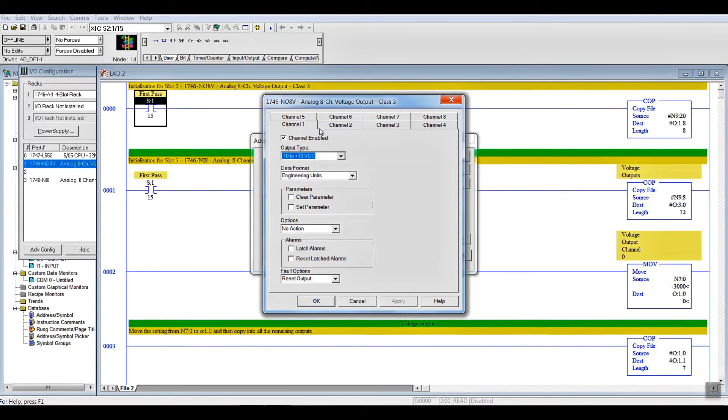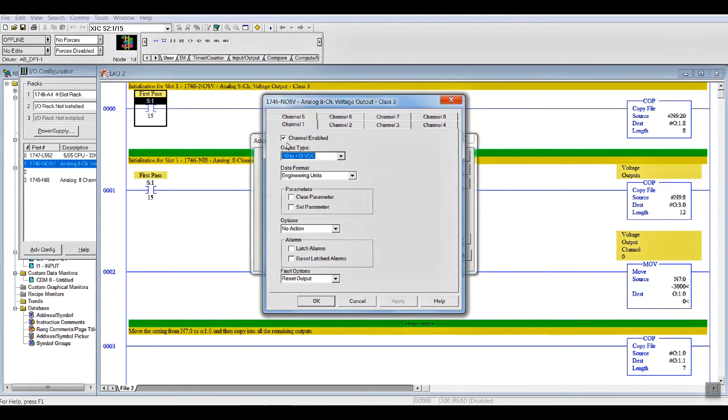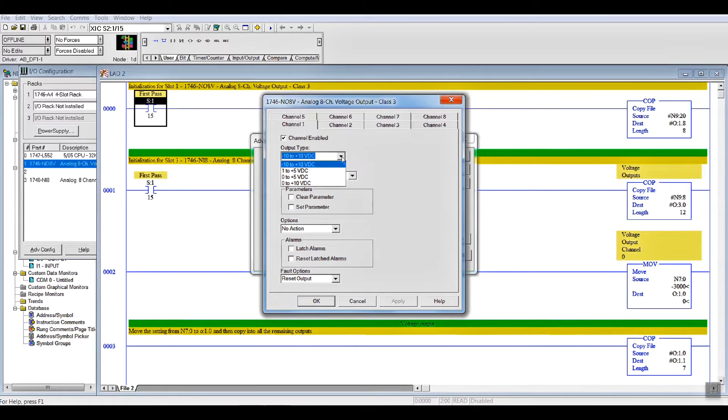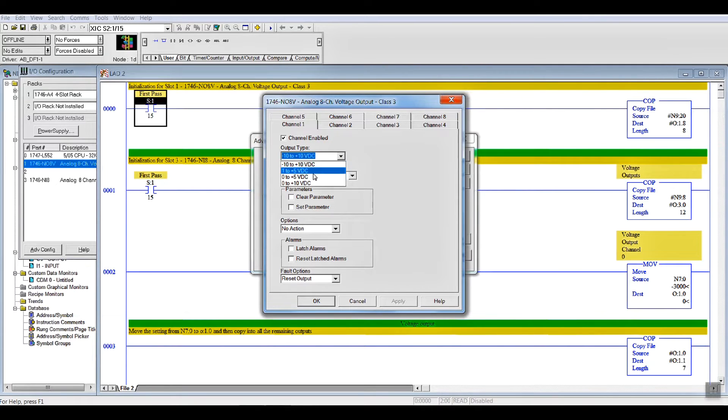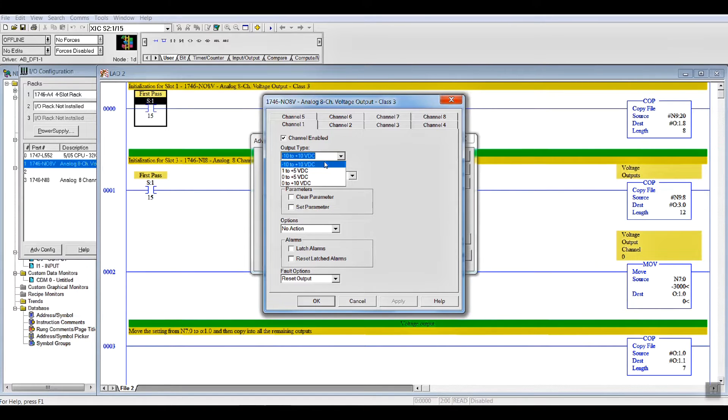Now, in this particular case, being it's an 8-channel voltage output, you have to enable the channel on each channel that you want. You have to pick the voltage output. Plus minus 10, 1 to 5, 0 to 5, or 0 to plus 10. In my case, I want to do plus minus 10 so I can test the input over the full range.